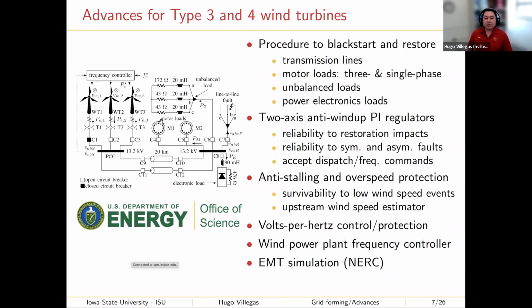And the reason I'm not using batteries here is that without batteries, the problem is tough. We wanted to solve the tough problem first, and then go to the easier one, that is, when using batteries. Of course, to do this, we also had to come up with an upstream wind speed estimator. Some of the features of this controller are volts-per-hertz control or protection. The survivability is achieved by dropping voltage at the terminals of the wind turbines. When survivability mode takes place, it's necessary to have tight control on the volts per hertz, because otherwise we can endanger the electromechanical energy conversion systems that are connected to the grid.